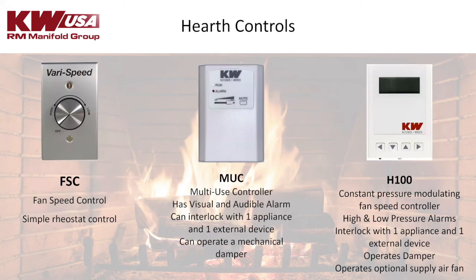These are the main controllers we use for the hearth market. The FSC is a simple rheostat controller that we use mainly for pizza ovens. But typically for fireplaces and for hearth, we're using the MUC, the multi-use controller, because it meets all those codes we talked about. It has an audible or visible alarm if the draft system fails. It can also interlock with the appliance, as well as an external device like a carbon monoxide detector, and it can operate your mechanical damper as well.